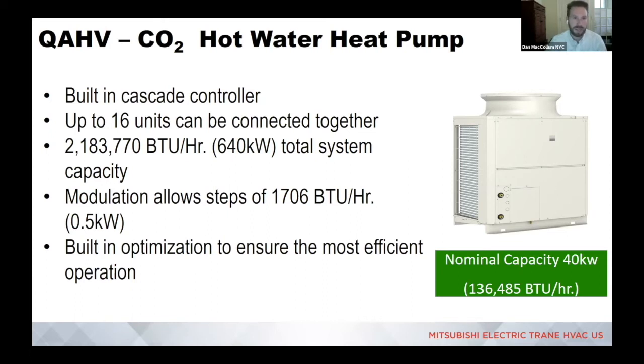We realize that certain jurisdictions have periods of time where energy costs are much lower, so it would be beneficial to be able to produce your hot water, let's say overnight, so that it's there in the storage tanks ready to go, rather than producing it during that building warm up, or, you know, the 6 o'clock to 8 o'clock slot where everybody's taking their showers in the morning.